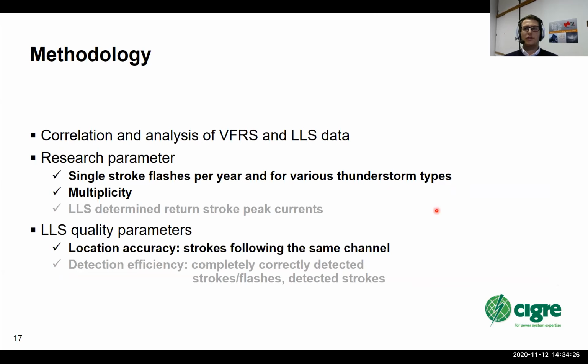Today, the single stroke flash percentage per year and for different thunderstorm types will be the most important, and also the mean multiplicity will be of interest. The LLS determined return stroke peak currents are parameters which were investigated too and can be found in my thesis again. For the LLS quality parameter, the location accuracies shall be discussed here. So the location accuracy is one of the two most important quality parameters or main parameters to classify the actual performance of such a lightning location system, sensor system.